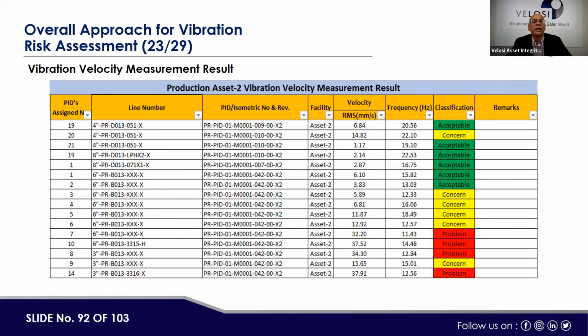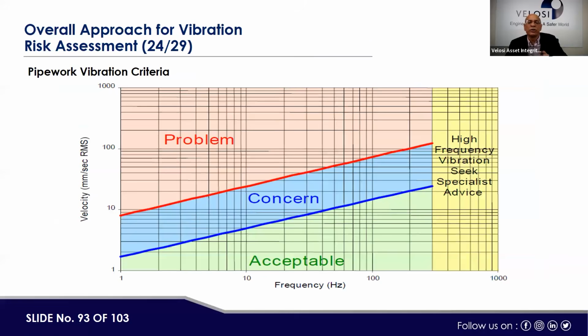Like here, in other parts other than the flare system, the problematic areas where velocity measurements were taken were 32, 37, 34, along with frequency in hertz of 11, 14, and 12. So you could see that if velocity is lower, even if frequency is a little higher, that is acceptable. But if both velocity and frequency are higher, then it goes to the unacceptable range. So this was basically the criteria of the Energy Institute that we used: acceptable, concern, and problem, with velocity and frequency together.